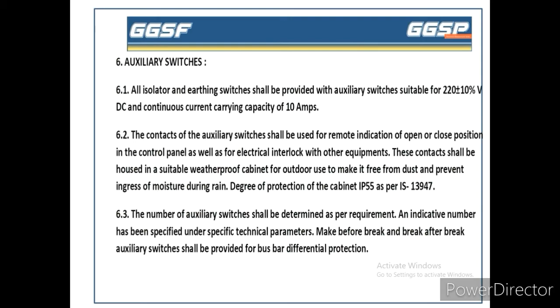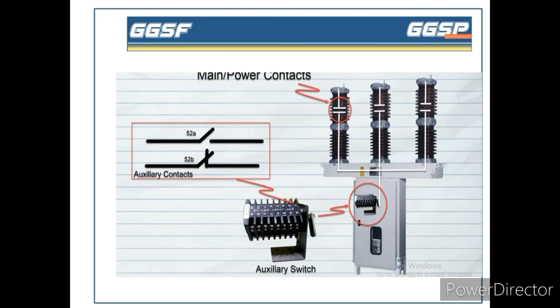Degree of protection of the cabinet: IP55 as per IS 13947. The number of auxiliary switches shall be determined as per requirement. An indicative number has been specified under specific technical parameters. Make before break and break before make auxiliary switches shall be provided for bus bar differential protection. This is a diagram of auxiliary switches.